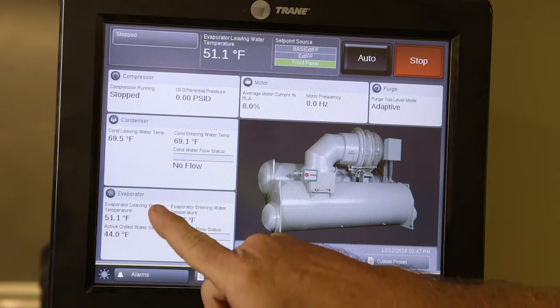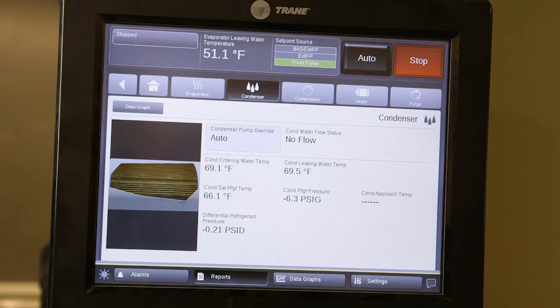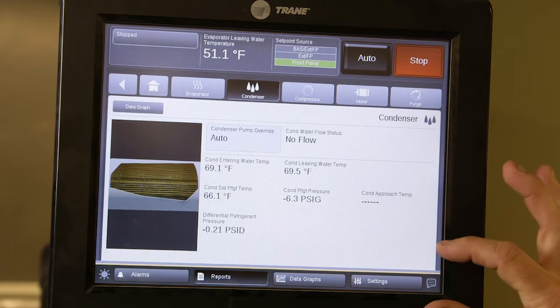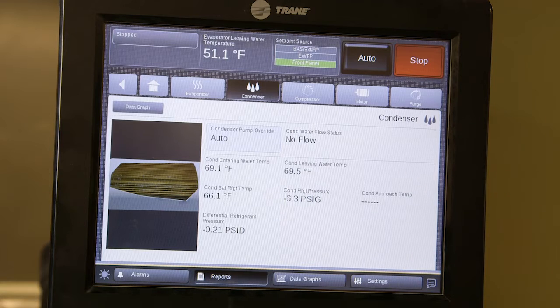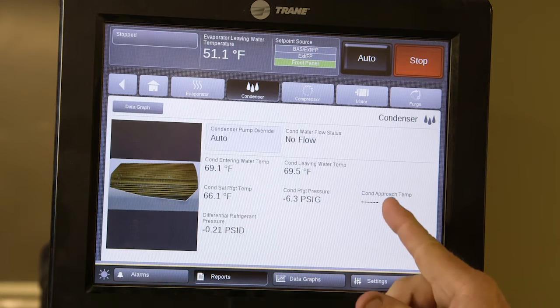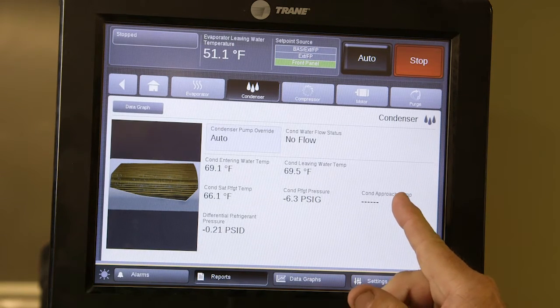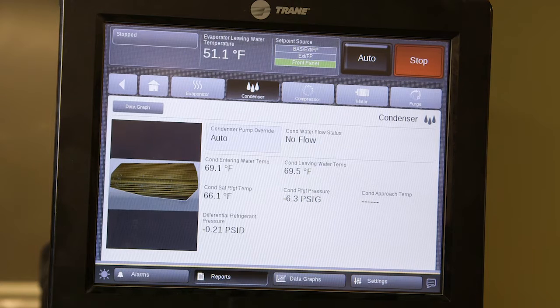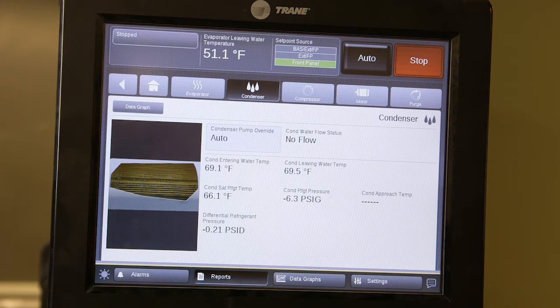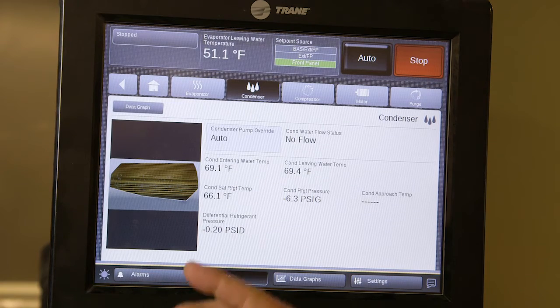From the main menu you can go to any one of these devices by clicking on it and it will open that screen. For the condenser screen, there is no second page. The approach temperature is shown here and is a good gauge to look at when checking your condenser tubes to see if your water treatment is satisfactory.